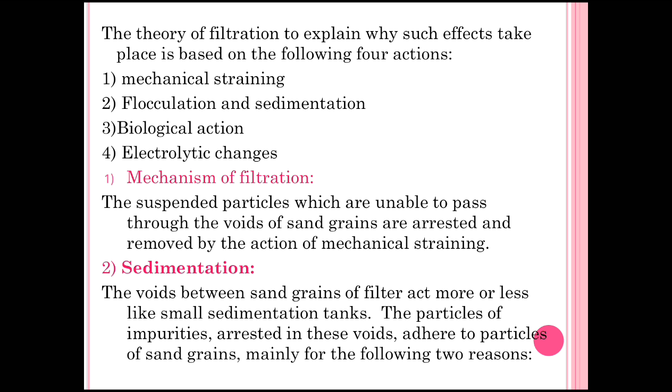Mechanical straining means when water is passed through sand particles, whenever three or more particles are attached to each other, there are small spaces between them, and those are called voids. Those voids do not allow the suspended particles or colloidal impurities to pass; they get arrested, removed or filtered by this mechanism, which is called mechanical straining.